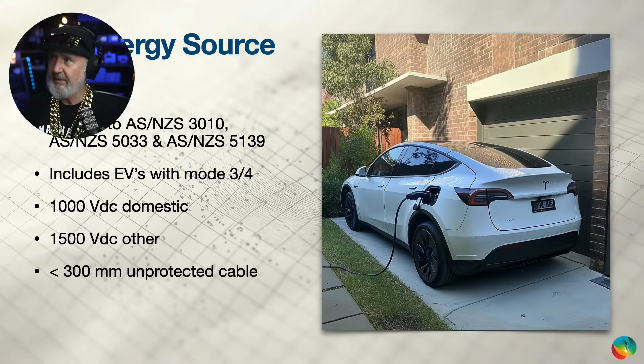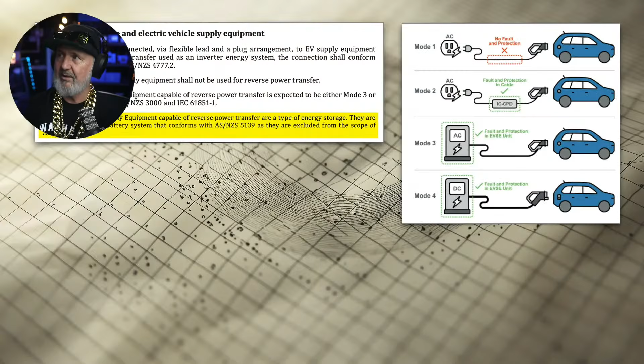Now, we've stated that you can only use mode 3 and 4 in the standard, let me explain those 2 modes. Here's a little diagram of modes 1 through to 4. Mode 1, I don't think it's even permitted in Australia and New Zealand - that's just a plug directly to your car with no fault protection. So pretty much all those chargers that come with your vehicle - I'm using the word charger loosely because they're EVSEs - actually has a little brick in the middle, and that brick provides fault protection to that cable, and it may well have a plug or a tethered cable to your device on the wall, your EVSE.